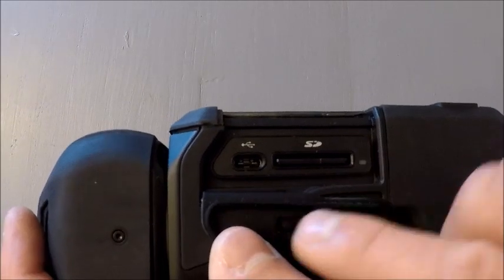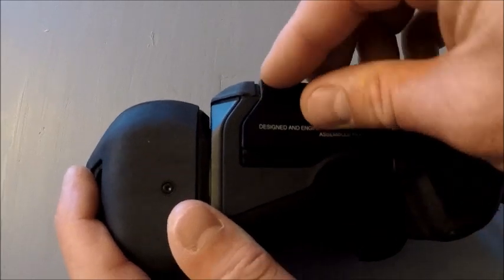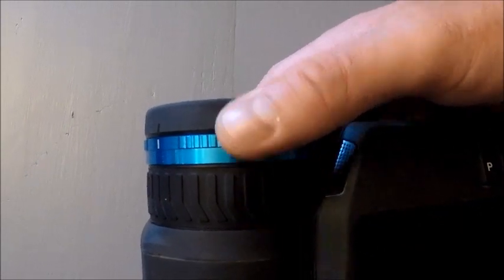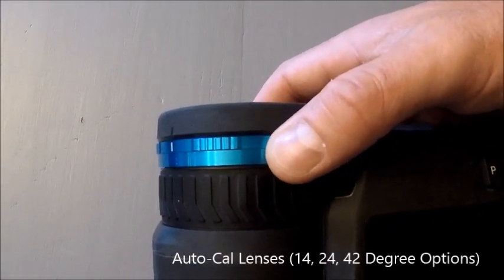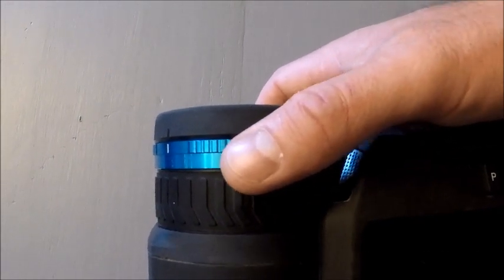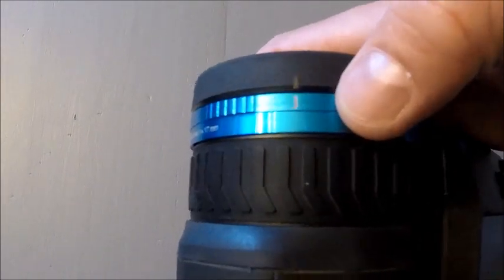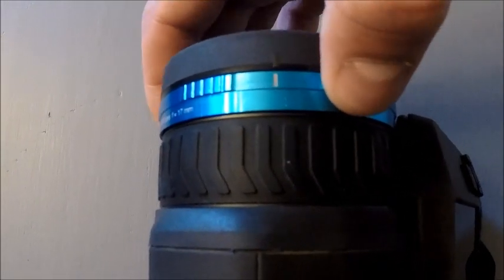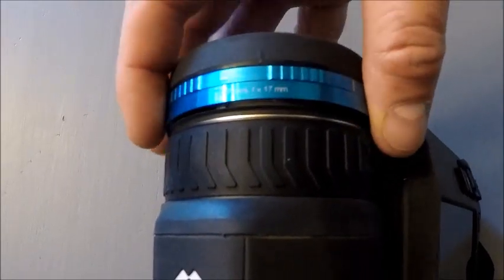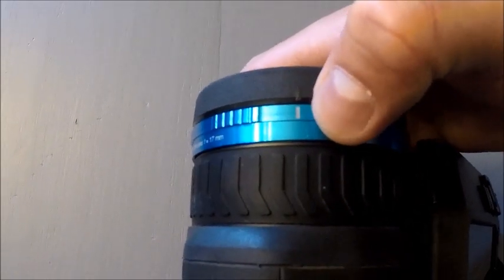On the bottom we have an SD card slot and our USB output or communications connection. On the lenses, just like our EXX cameras, we have an Auto Cal lens feature, which means you can get additional lenses calibrated to the camera without having to send the camera and lens back to the factory. To remove the lens, you have two lines — a white and a black one. Take a quarter turn on the ring and pull it apart. To reattach, line up the black and white lines and it's just the opposite.